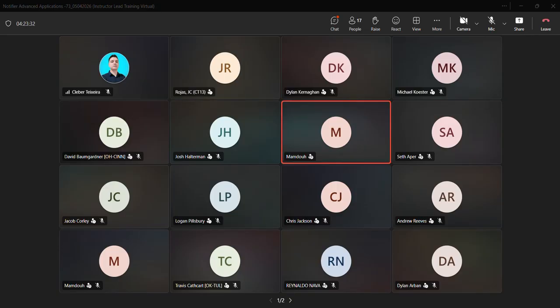Correct. So let's say I have the 5th floor in alarm, 4, 5 and 6 are going to be in evac, and then the rest of the building is going to be in alert. Correct. You can use the same logic equation that'll trigger the evac message, but you've got to make sure that those are, as always, separated. Okay. In that list, when you get to the PAM points, you should be able to see them there separated.